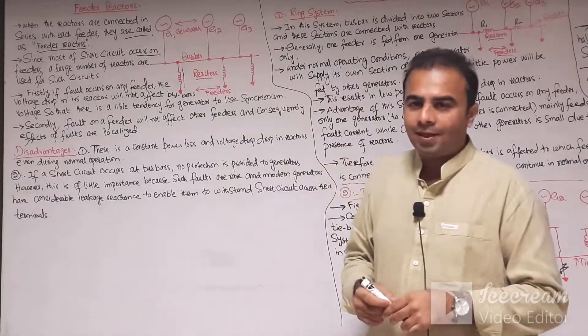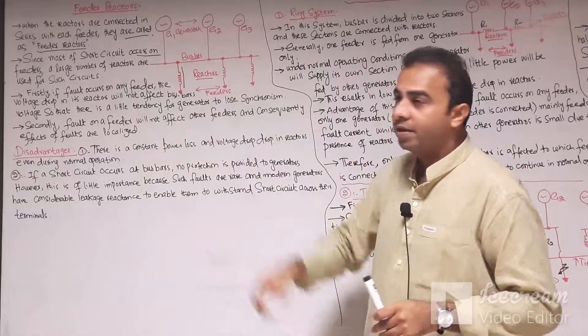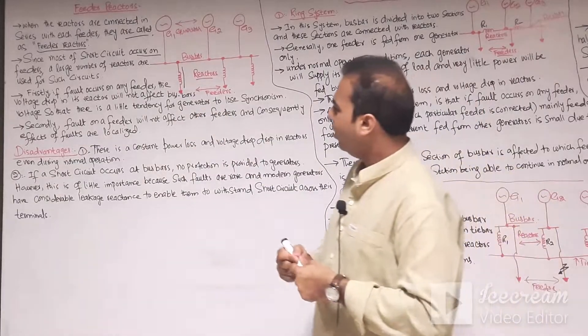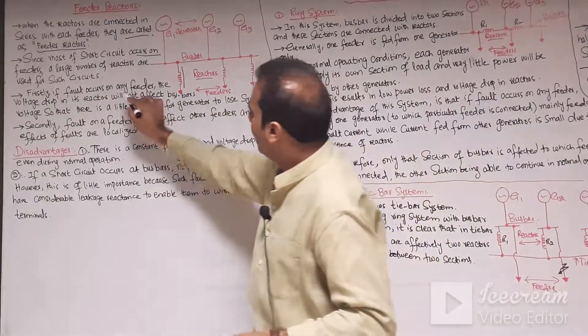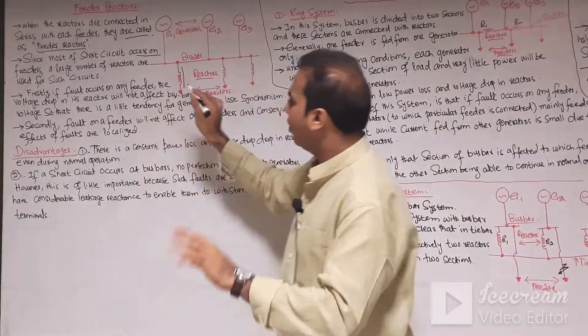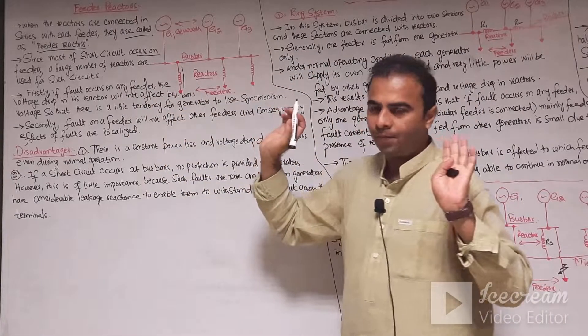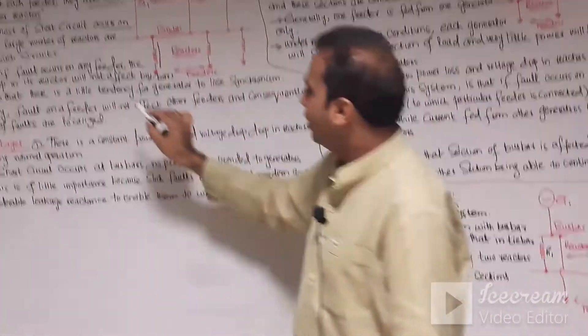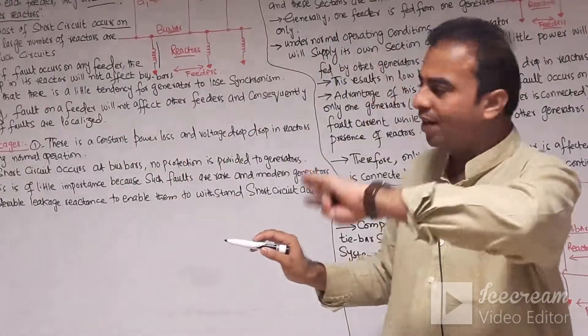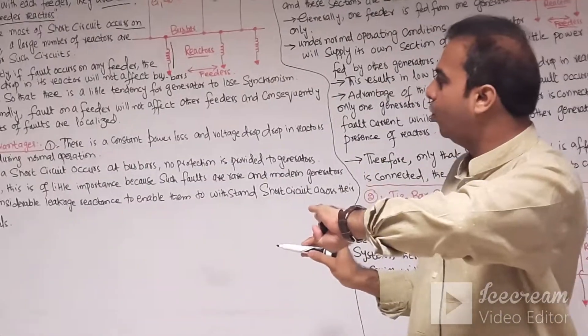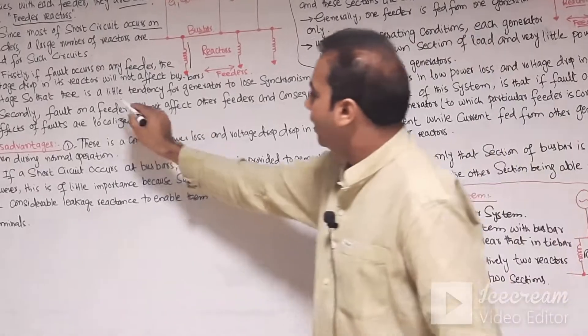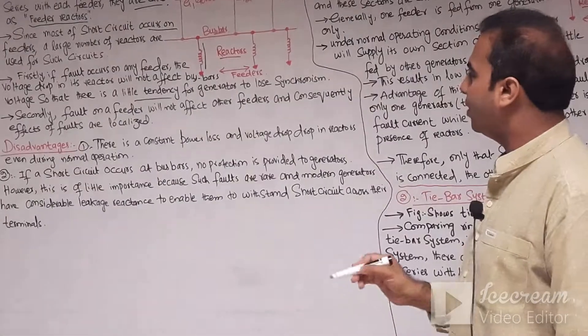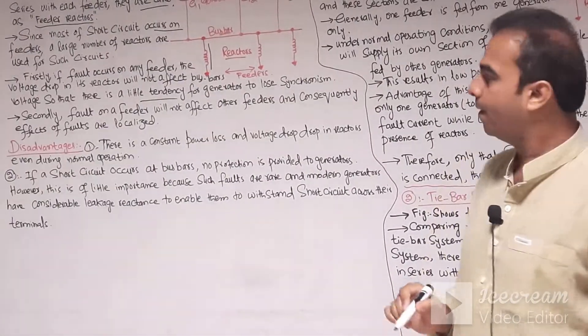Let us discuss the advantages of the feeder reactor. Firstly, if a fault occurs on any feeder, the voltage drop in its reactor will not affect the bus bar voltage, so there is little tendency for the generator to lose synchronism.